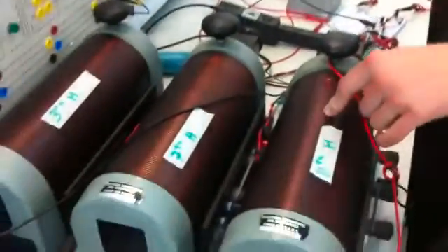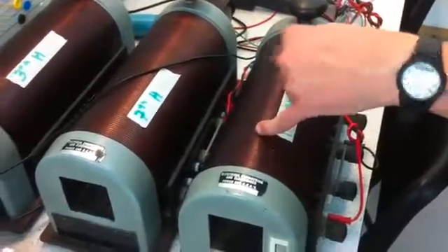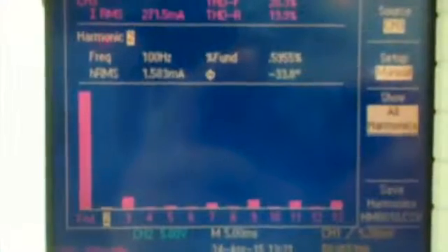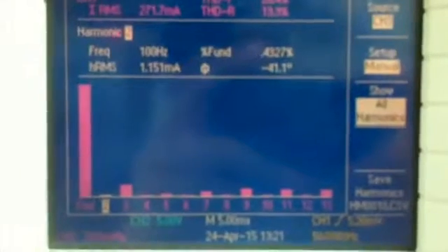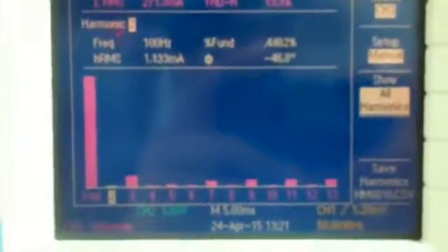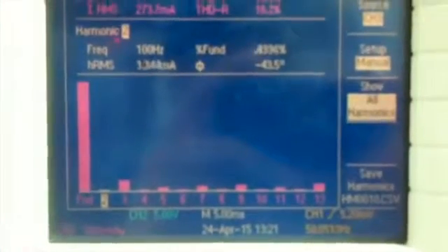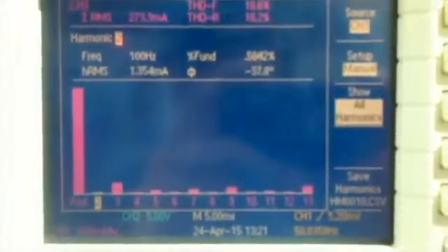All right, so that's the 7th harmonic filter, and now I'm going to apply the 11th harmonic filter. It's not that relevant with respect to the spectrum, as you can see over there, but I modeled it in PSpice, and the 11th harmonic was still quite prevalent at that time. So I'm just going to apply the 11th harmonic filter now to show you what that does to the spectrum. So now the 11th harmonic is reduced. The amount of reduction is significant, but you won't be able to see it there because the spectrum analyzer hasn't shown much of the 11th harmonic to begin with.